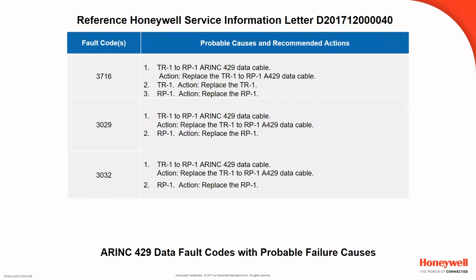And a 3032 could be logged if there are errors with serial communication status like receiver overflow or receiver sync error or transmitter sync error, etc. And this fault could lead to a reset of the main processor. And if this fault exists, then we recommend to check and replace the ARINC 429 cable as the first troubleshooting step. And the second would be to replace the RP.